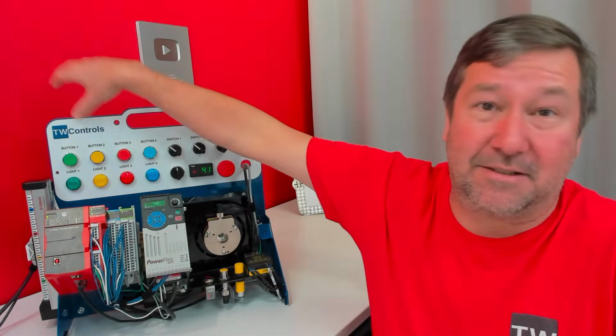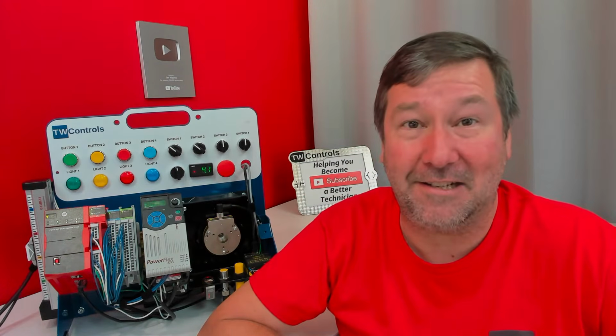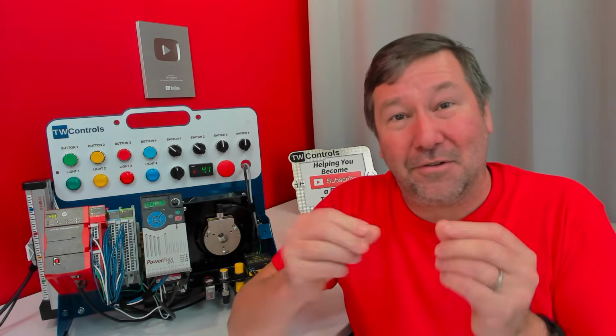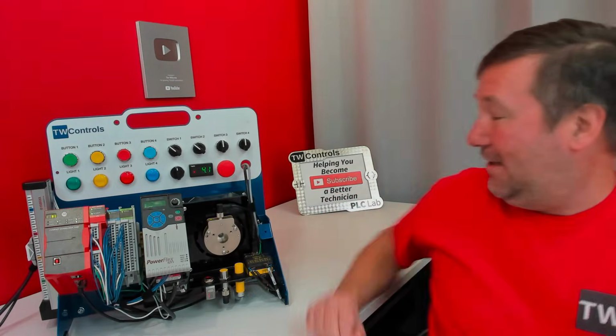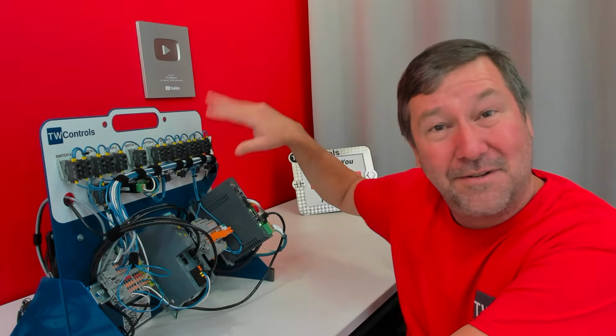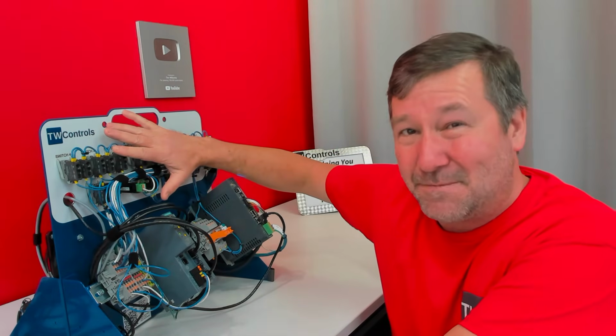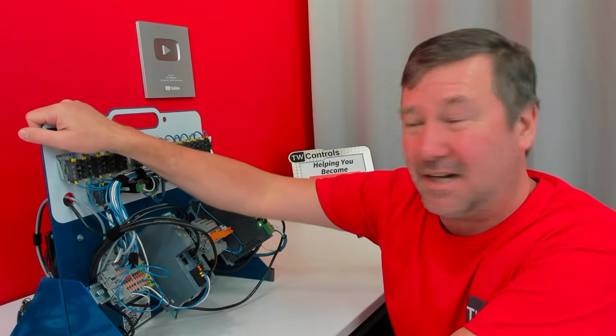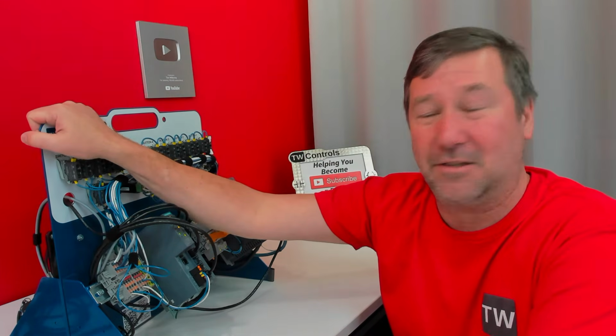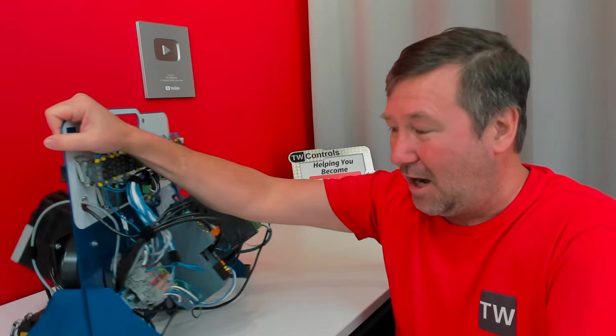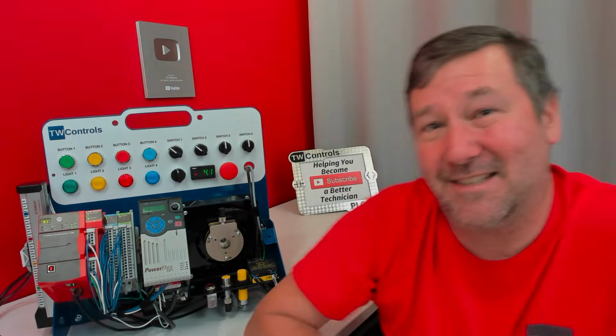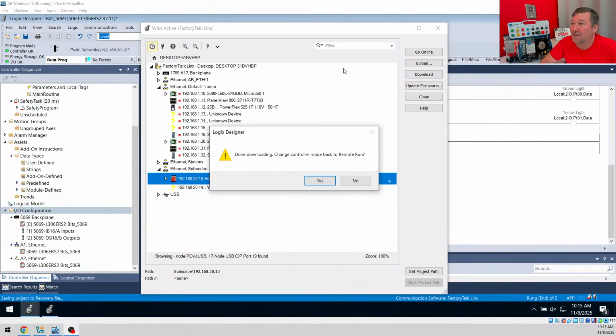As a technician, when I press this green button and it doesn't work, the only thing I need to know is that local thingy. So the local address is the piece, and this is really the piece I see missing from most people's programming classes. In fact, instructors, I know a lot of you are using other trainers. Well, this is my video trainer. It is wired, but our trainers are not wired. That's really the downfall, I'll say, of almost every trainer out there on the market: they're pre-wired. They're made to look pretty. But no, we need to understand the wiring piece. And when we throw aliases in there right away, we just shoot ourselves in the foot as far as troubleshooting. All right, when we're done, we're going to get a prompt here to go back into remote run.